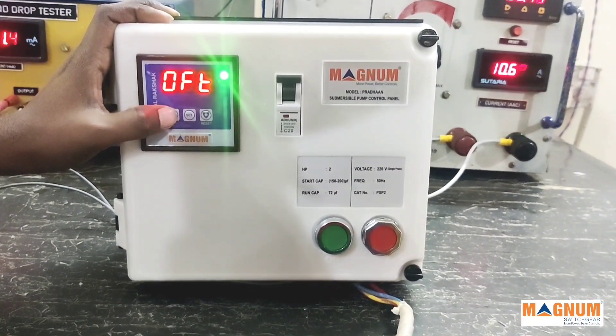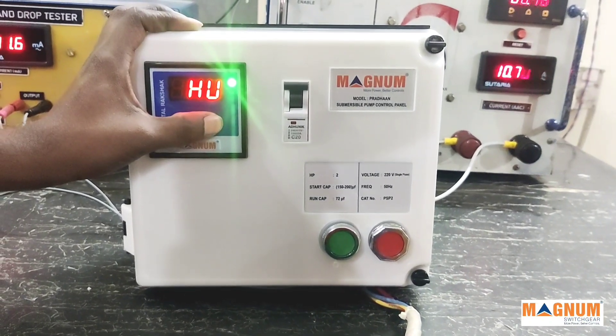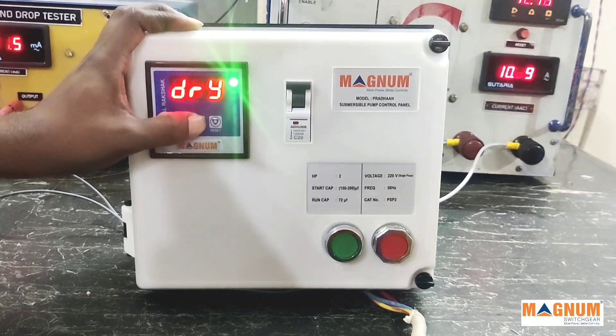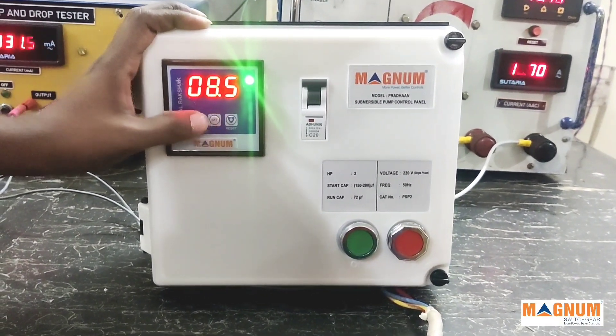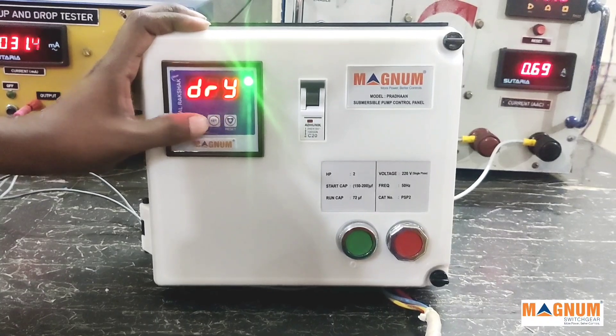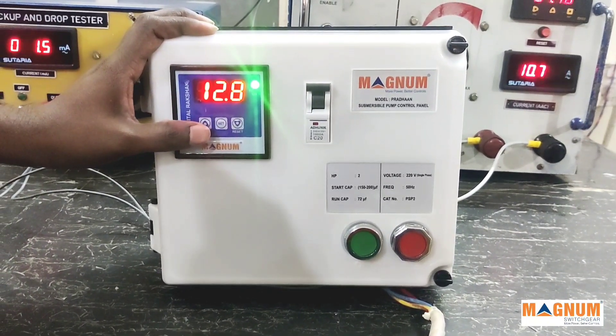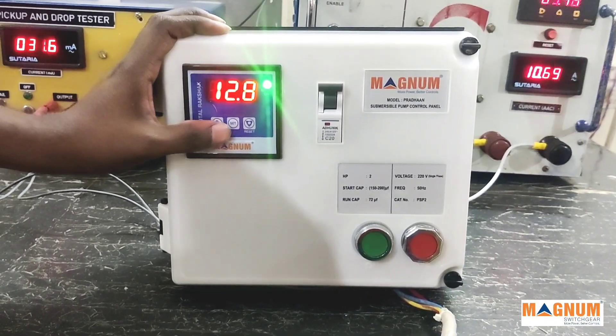dRY will show you the dry run current set by the meter, which is 8.5 amps in this case. OL will show you the overload current set by the meter; in this case it is 12.8 amps.